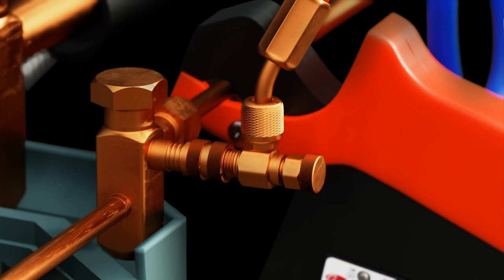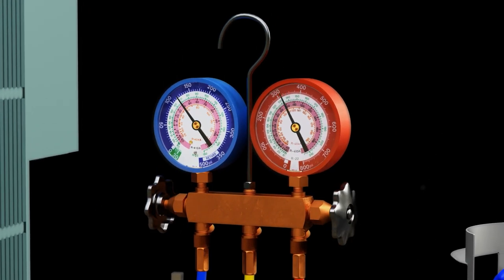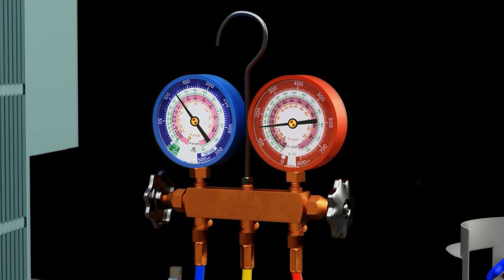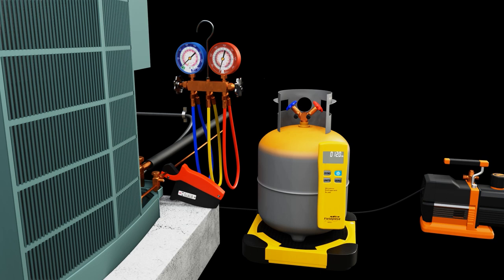So now we're safe to go ahead and disconnect everything. The first thing we do is we back out our core depressor. And then we feed that refrigerant that's in the gauges and hoses back into the suction side so that we don't waste that refrigerant. Shouldn't be a significant amount of refrigerant, but we just don't want to waste it. Then we can safely disassemble everything.